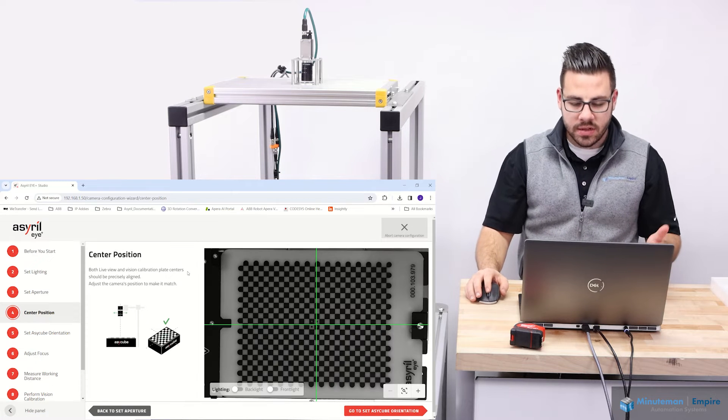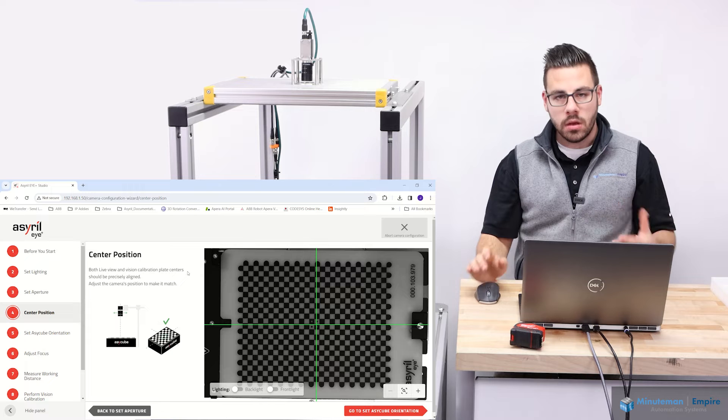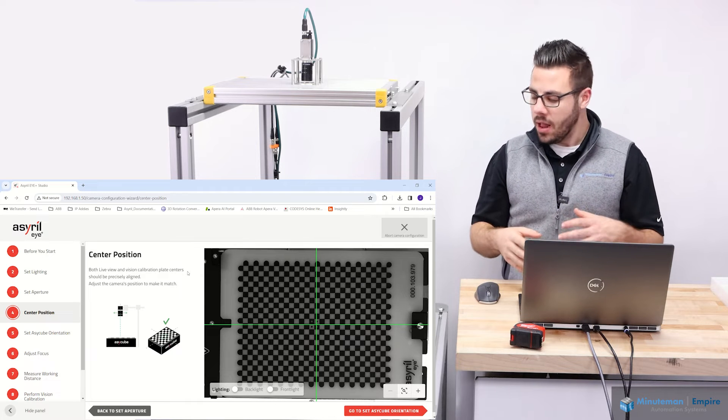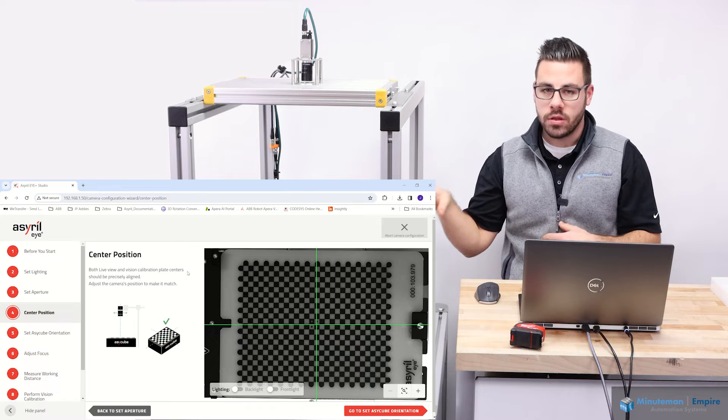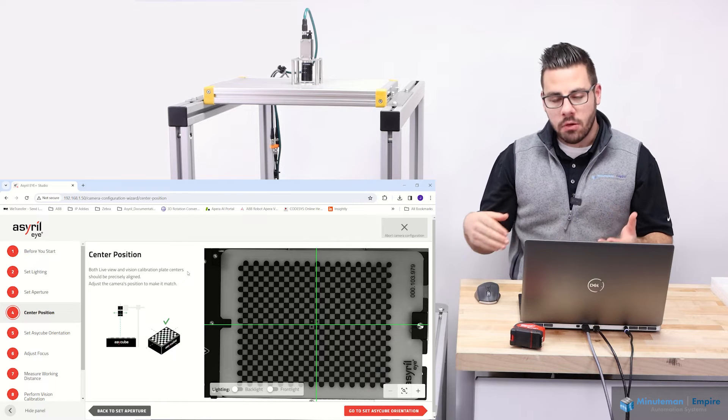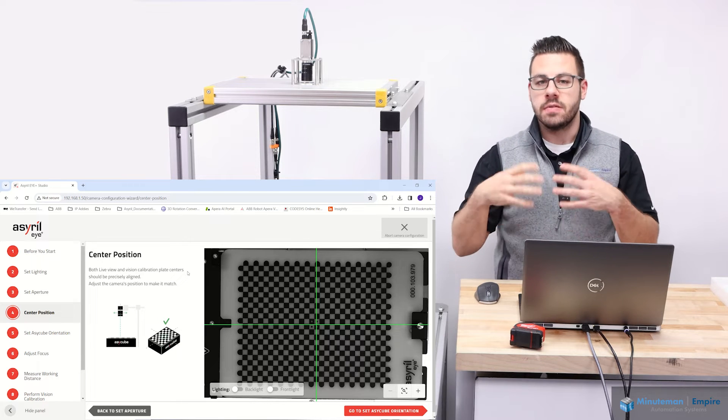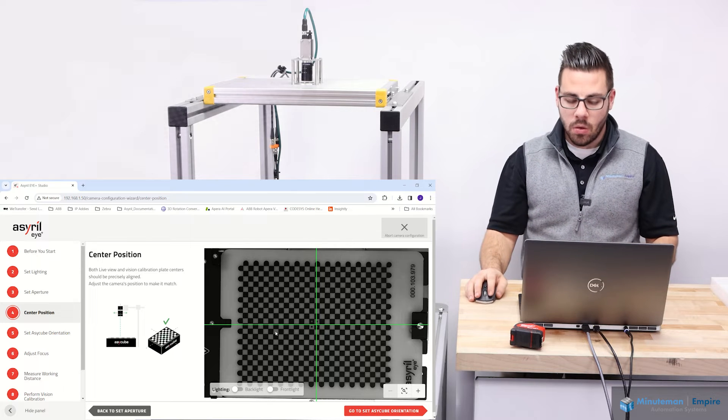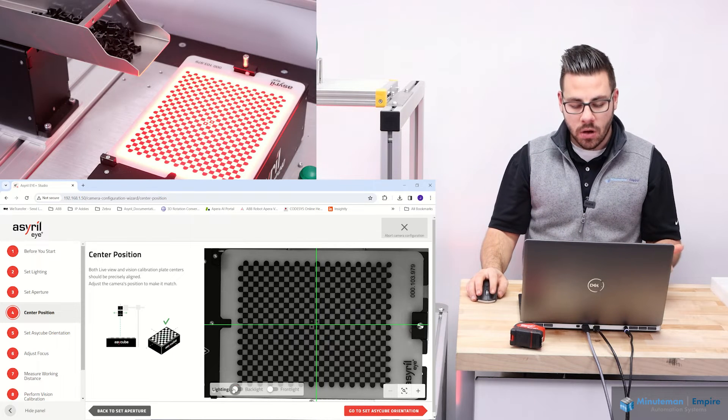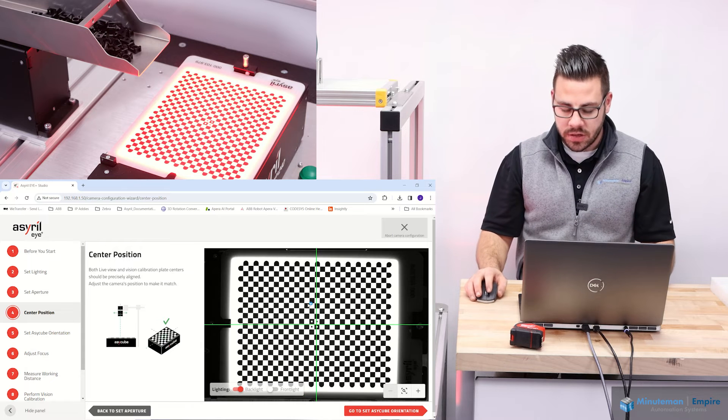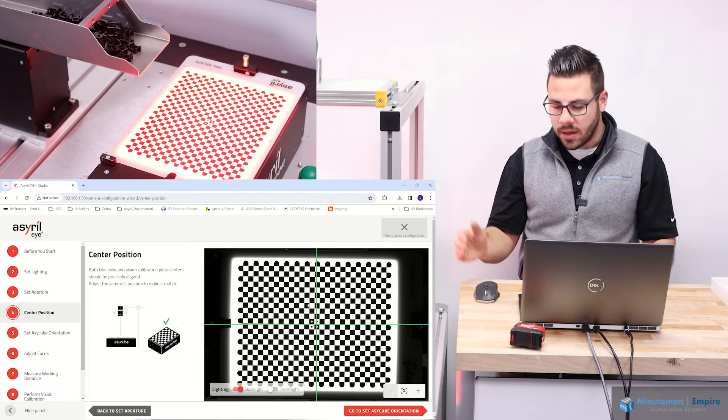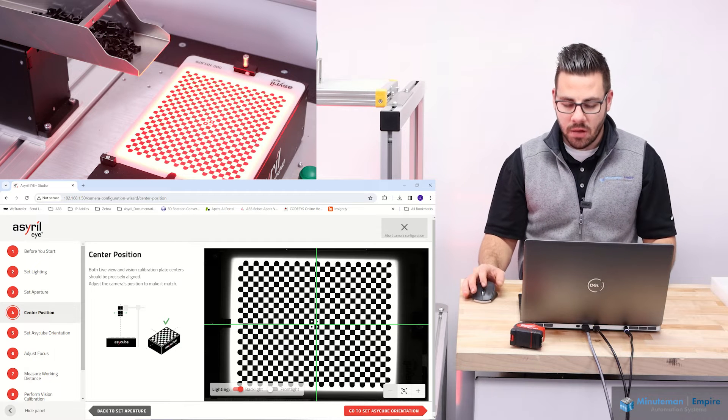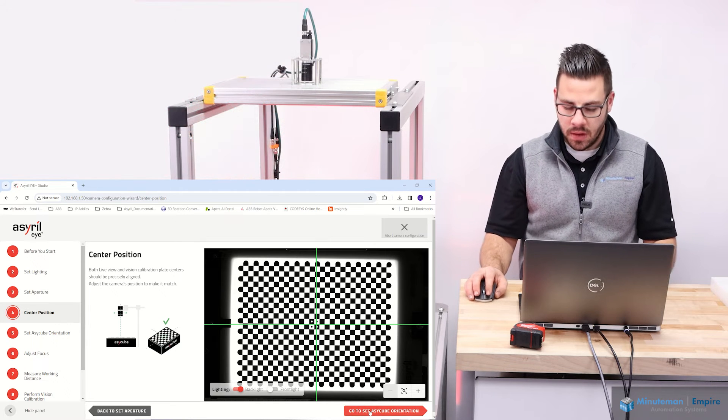Now we want to set the center position. It's critical if you are doing a robot pick and place application that these crosshairs align with the fiducial on your plate. However, for the demonstration purposes of this video, it is not absolutely critical. So what we have here, I'm going to call good enough for the purposes of this demonstration. I went ahead and turned the backlight on so you can really see the contrast between the plate itself and the crosshairs.